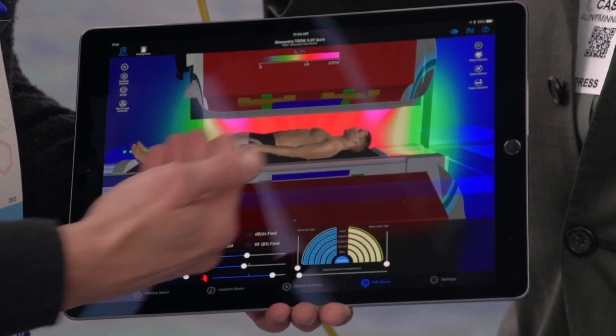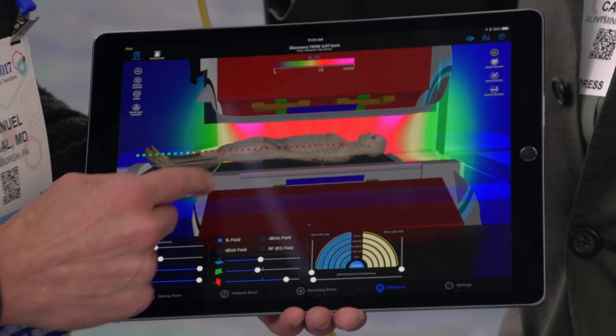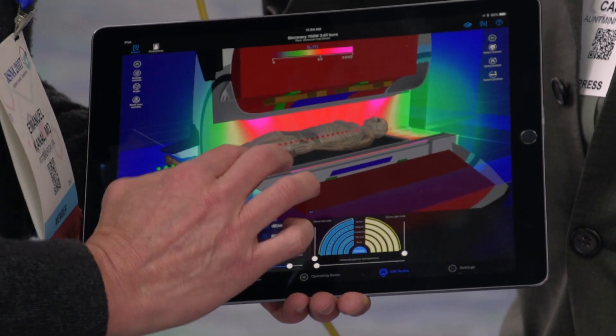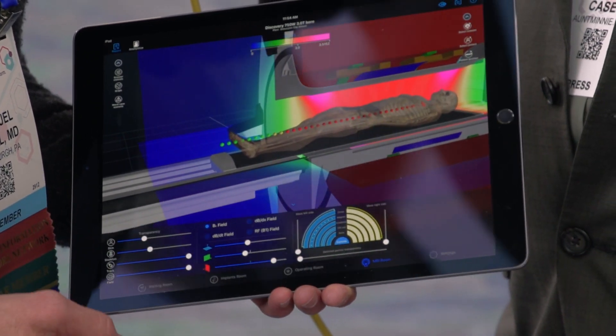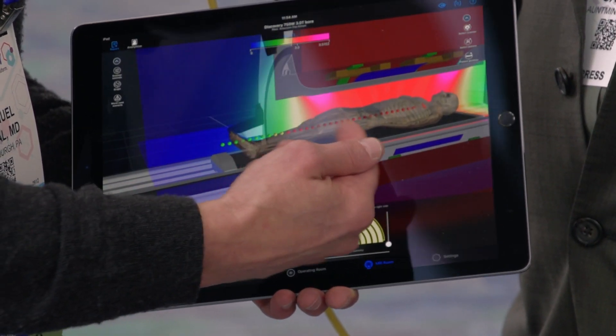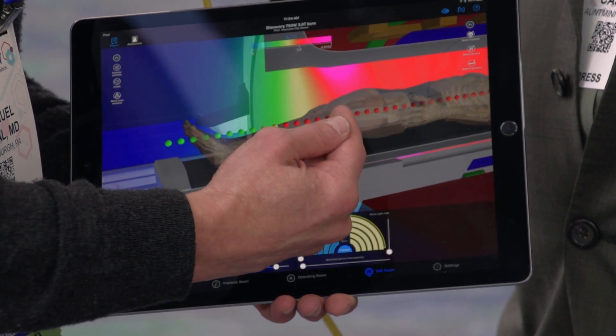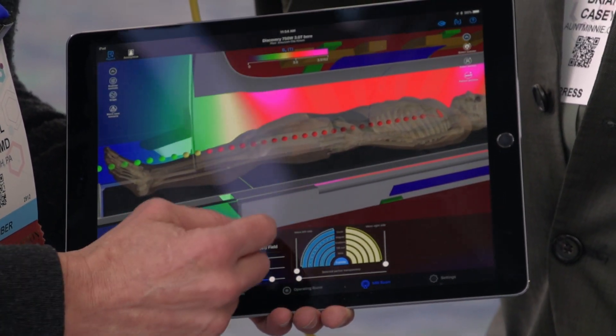And finally, this patient has within them an implant. Let's make them invisible, and you'll notice that there's the pacemaker in this patient. Notice the colored balls — this pacemaker may be approved, for example, up to 1.5 Tesla. As the field gets stronger and stronger, it shows you that it's going from green to yellow to red, because now it's exceeding a published safety threshold for that pacemaker.